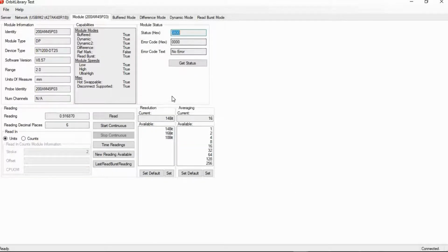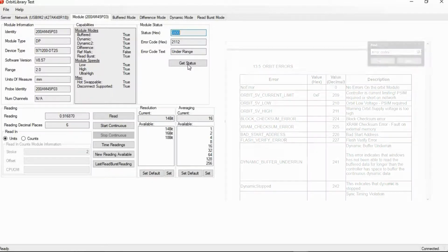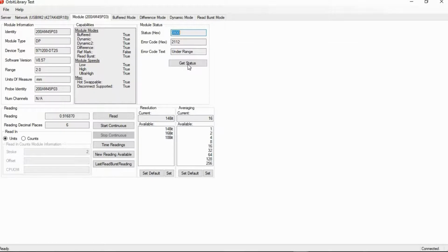Now, another feature too is in the upper right-hand corner here, the module status. You'll see there's a status hex, error code, and error code text. This can be helpful, especially if you're getting perhaps a red blinking light, but you're not quite sure what the problem is. If you click here, get status, so for example, here right now the probe is under range, the error code comes back 2112. There's actually a particular error code for several different types. So if you go to the Orbit software manual, you'll see an entire list right there as shown on the right-hand side. This is also something where a command can be sent to the module and it will send back an error code, so you can even find out in your own software package.